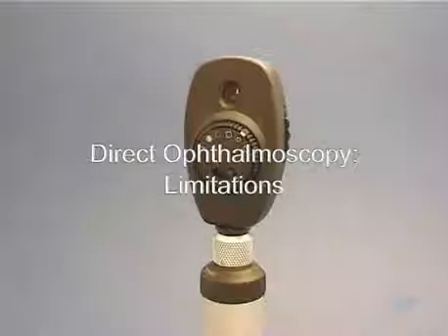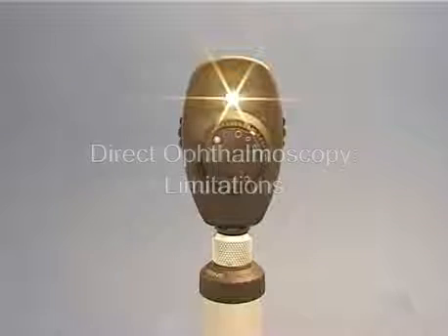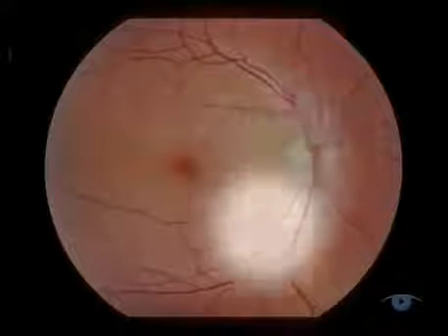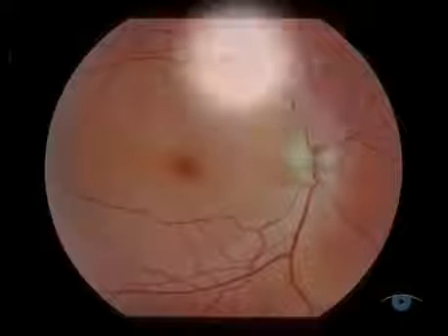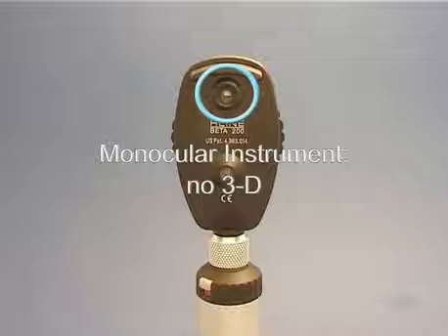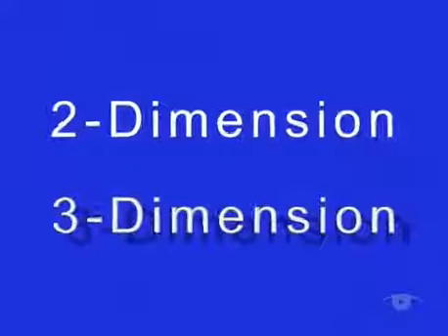You've now completed your examination. You should also be aware of the two principal limitations of this technique. The first is that the high magnification and small field of view mean that you have to build a collage of the whole fundus in your visual memory and then mentally stitch it together — this only becomes reliable with regular practice. Secondly, the direct ophthalmoscope is a monocular instrument and can therefore only ever give you a flat, two-dimensional image, which imposes limits on your accurate judgement of height and depth, which require stereoscopic vision.